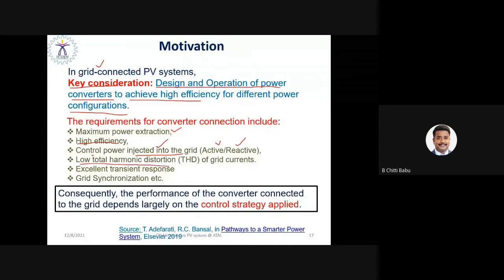And it should have a lower total harmonic distortion, because as we use the inverter, it is an inherent property with non-linear and PWM switching, and again we have a non-linear electronic load that will be connected at the point of common coupling. So due to the nature of the load and the inverter, the output current of the inverter inherently contains lower order harmonics. So we have to employ a control technique on this inverter in order to reduce the harmonic current present on the inverter output side, right? So ultimately the grid current should have a lower total harmonic distortion. As per the IEEE 519/2014 standard, it should have a THD of less than 5%.